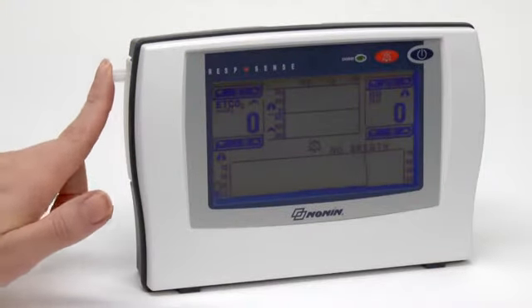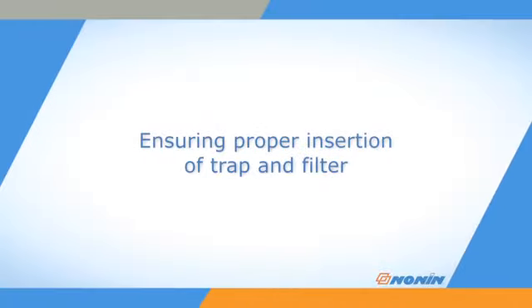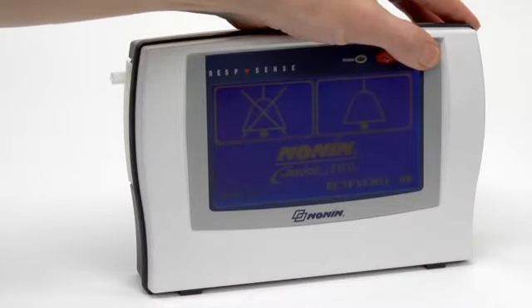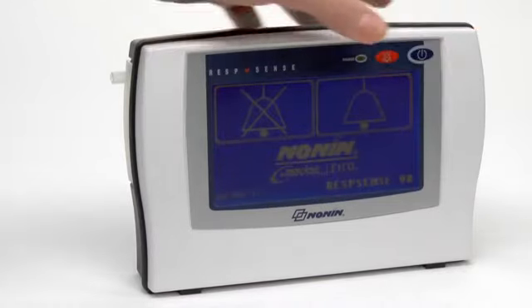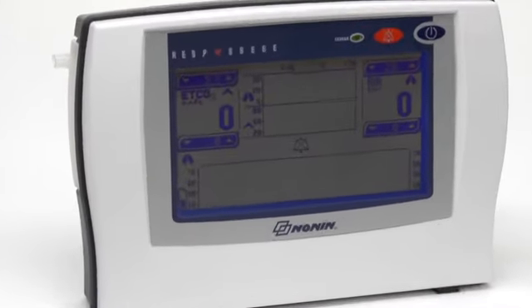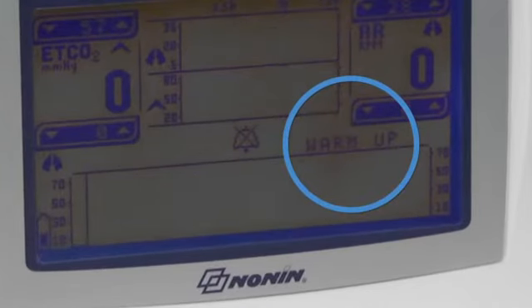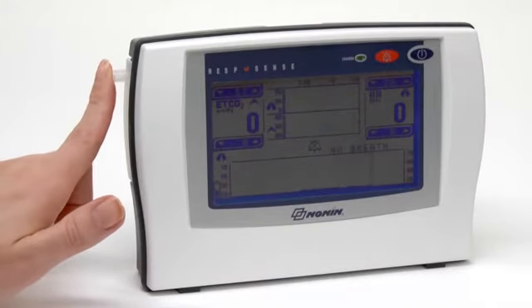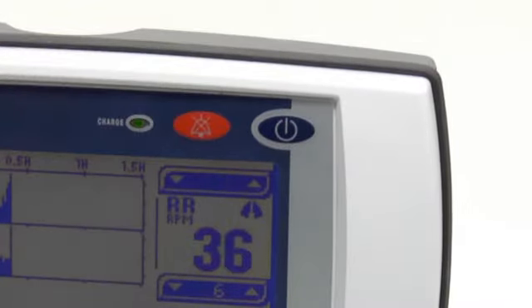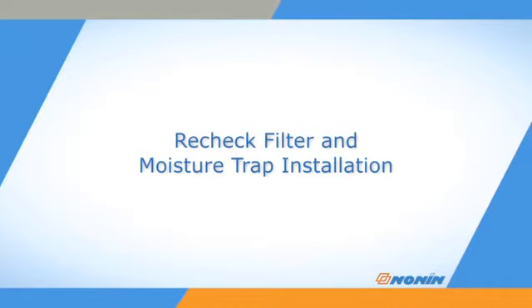There are several steps you can take to ensure proper function of the RespSense or LifeSense monitor before and during operation. To ensure the filter and moisture trap are properly installed, turn the unit on and start without connecting the sample line cannula. Disable the alarm. You will see warm up and no breath displayed as the unit turns on, and the pump will be running. Press your finger over the stem where the sample line attaches to the filter and trap assembly. Within a few seconds, you should hear the pump slow and see the occlusion alarm. Press the Alarm Reset button to clear the alarm. If you do not see the alarm within 5 to 10 seconds, recheck the installation of the filter and moisture trap.